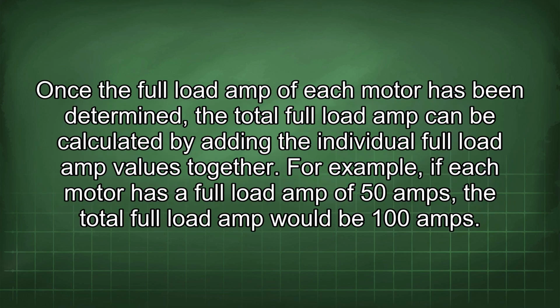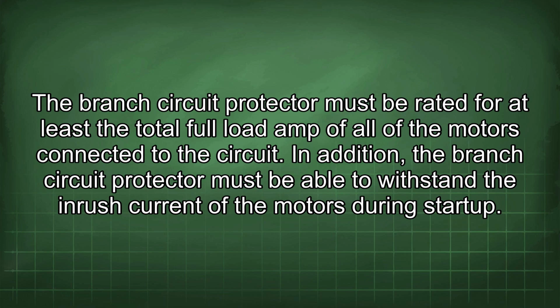Once the full load amp of each motor has been determined, the total full load amp can be calculated by adding the individual full load amp values together. For example, if each motor has a full load amp of 50 amps, the total full load amp would be 100 amps. The branch circuit protector must be rated for at least the total full load amp of all of the motors connected to the circuit.